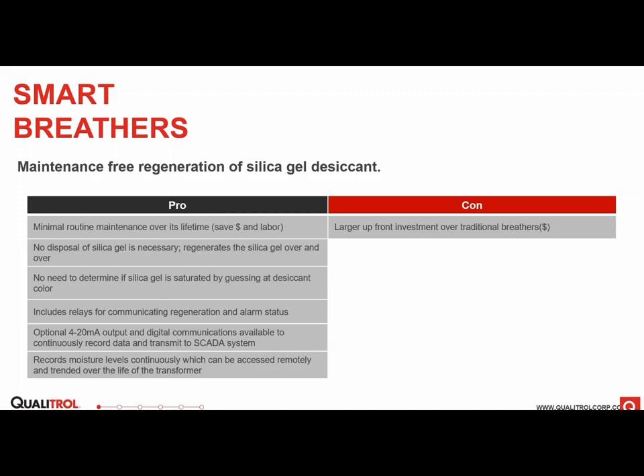And you don't need to guess if the silica gel is saturated by looking at it, because there are sensors that can determine that on their own. And then you also have the added benefit of data logging or communications for trending that data. And then the one downside is that they are a little bit more costly to install up front. So it's a larger investment, but it pays out over time by eliminating the maintenance costs and the time on site.